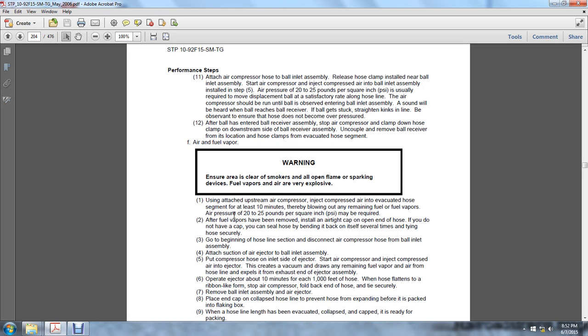Using the attached upstream air compressor, inject compressed air and evacuate the hose segments for at least 10 minutes, thereby blowing out any remaining fuel vapors. Air pressure of 20 to 25 pounds per square inch may be required. After the fuel vapors have been removed, install the air cap on the end of the hose, and if you do not have a cap, you can seal the hose by bending it back into itself several times and tying the hose securely.